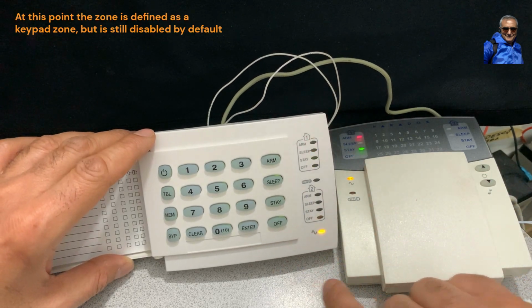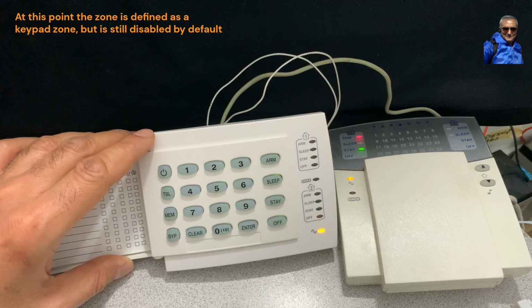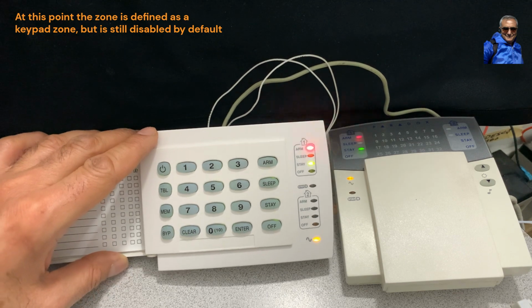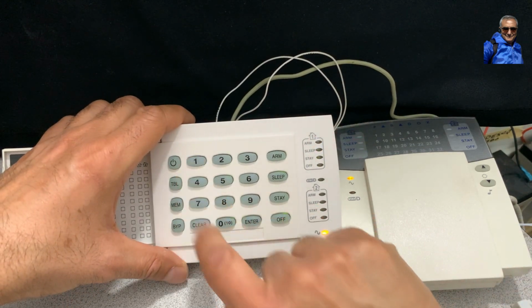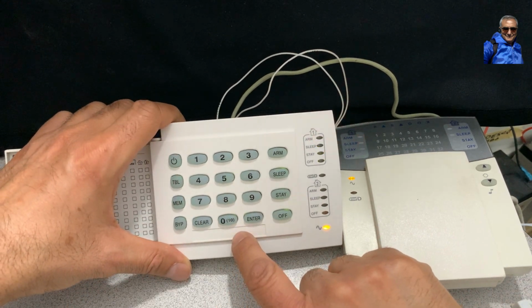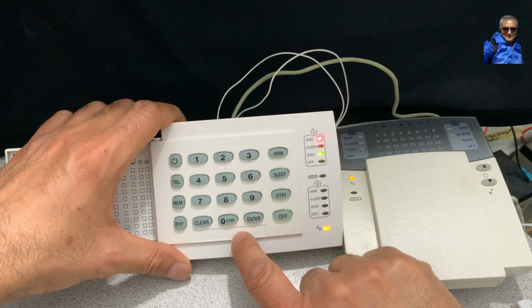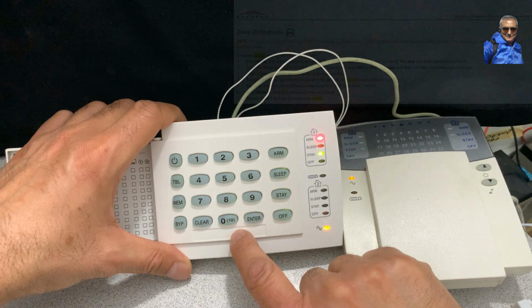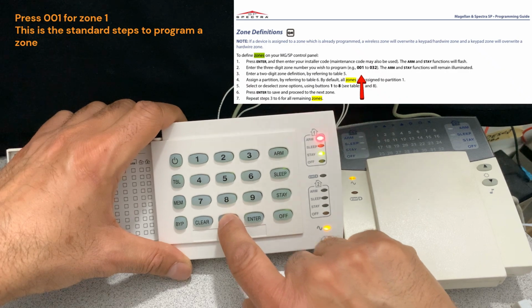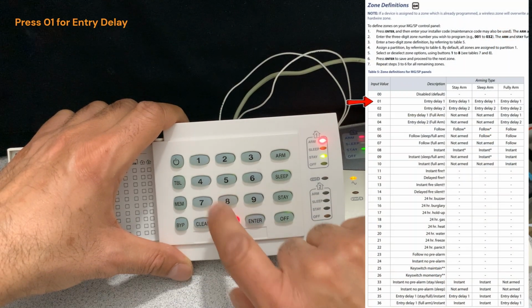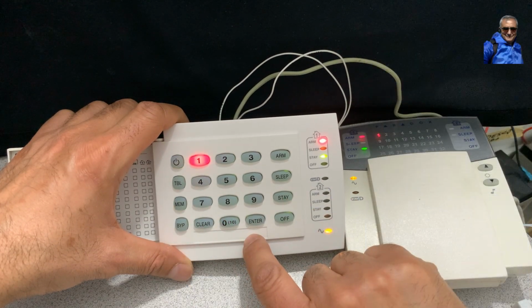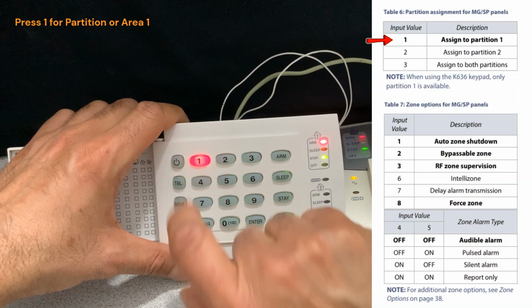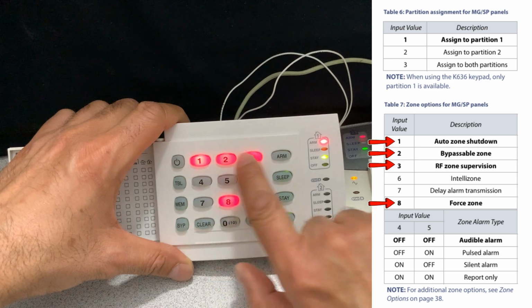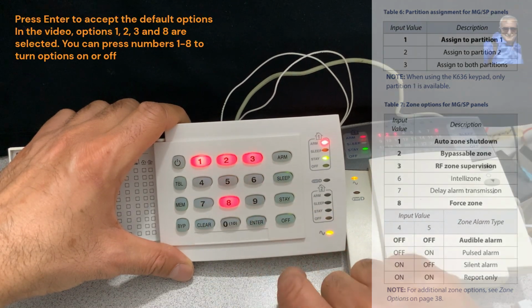At this point, Zone 1 is defined as a keypad zone, but it won't do anything until you complete your zone definitions. Let's define Zone 1 to be an entry delay zone in Partition 1, and we will leave all the rest to default values. To do that, press 001 for Zone 1. Press 01 for Entry Delay Zone. Press 1 for Partition or Area 1. Press Enter to accept all default options.